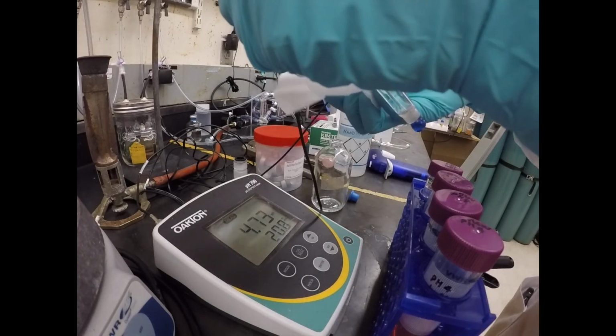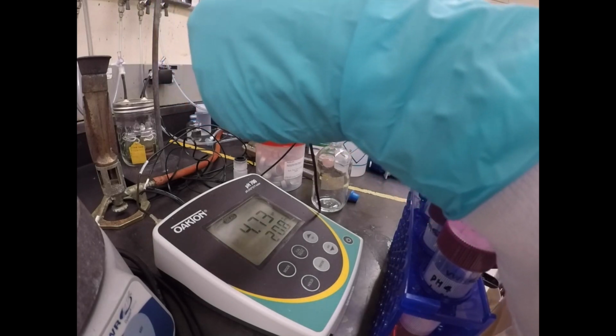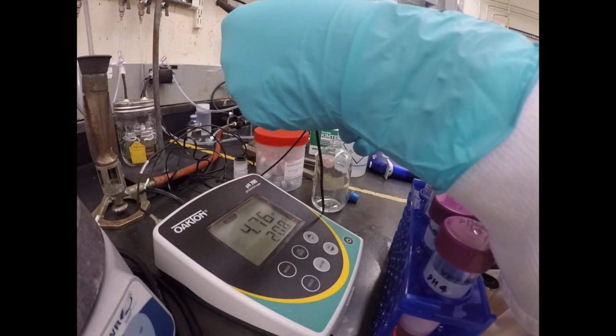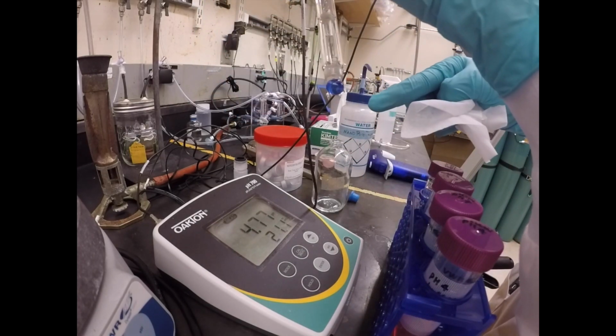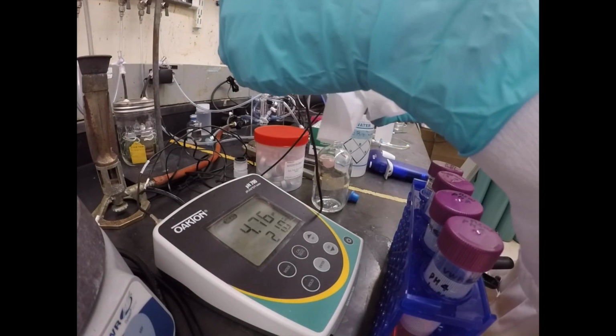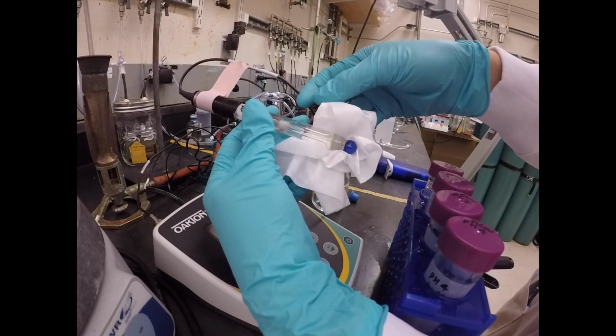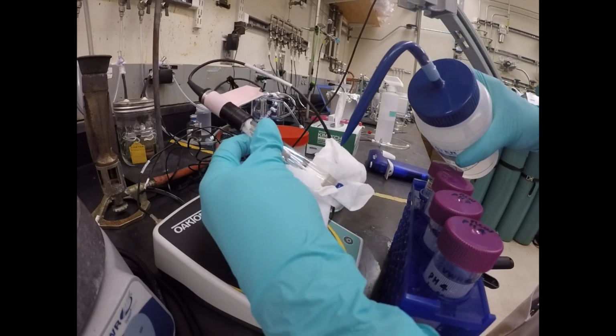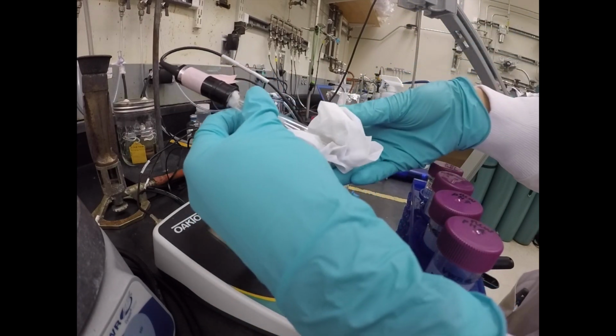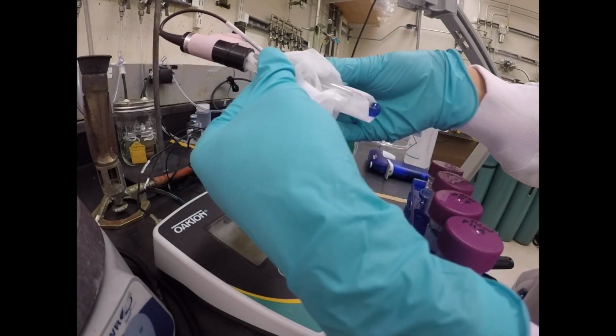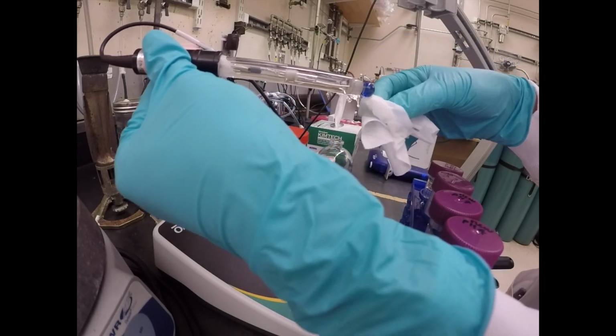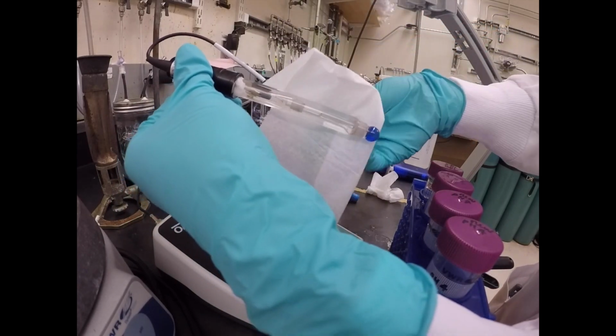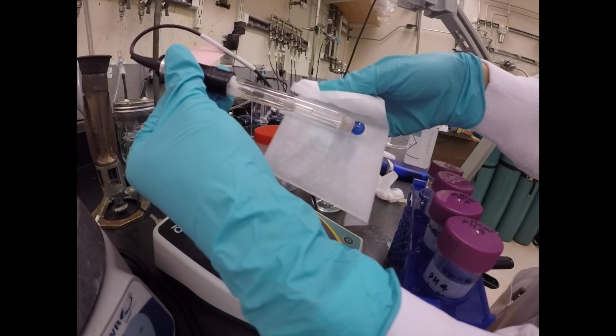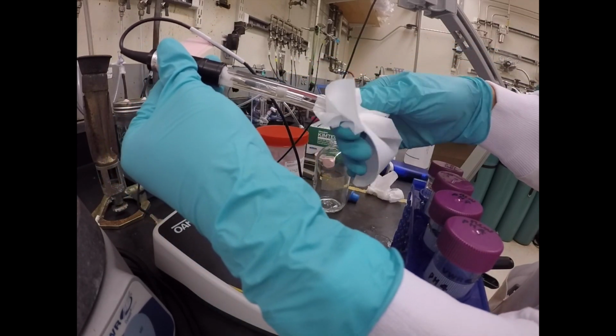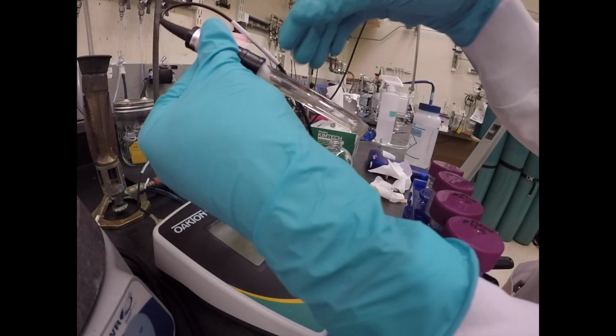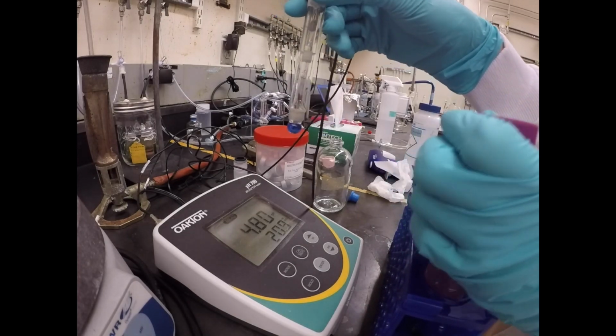And you're just going to give it a few rinses with nano pure water and Kim wipe. So it's important here to not touch the probe again, this blue part, with anything other than the Kim wipe. So usually I hold it like this and add some ultra pure water around the tip and just gently rinse the tip of it. After you do that, it's also important to remove the residual water from the surface with a new Kim wipe, because you're going to be submersing this in the pH solution, and you don't want to dilute your standard solution. So this can now go into pH 4 standard solution.